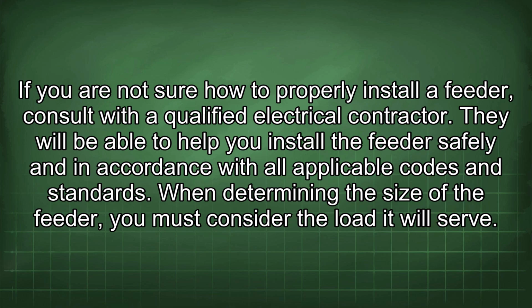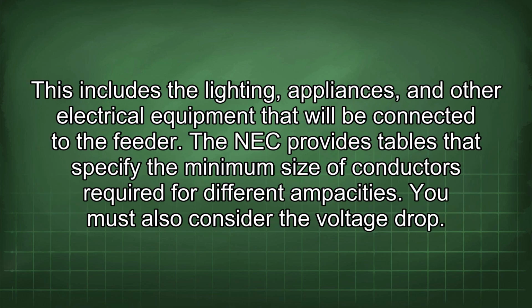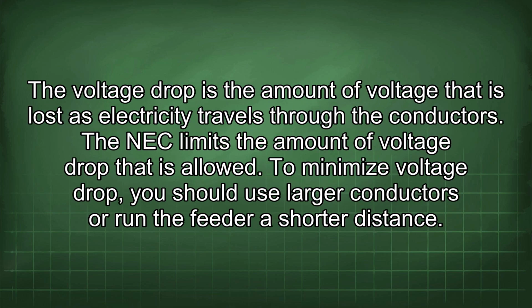When determining the size of the feeder, you must consider the load it will serve. This includes the lighting, appliances, and other electrical equipment that will be connected to the feeder. The NEC provides tables that specify the minimum size of conductors required for different ampacities. You must also consider the voltage drop. The voltage drop is the amount of voltage that is lost as electricity travels through the conductors. The NEC limits the amount of voltage drop that is allowed. To minimize voltage drop, you should use larger conductors or run the feeder a shorter distance.